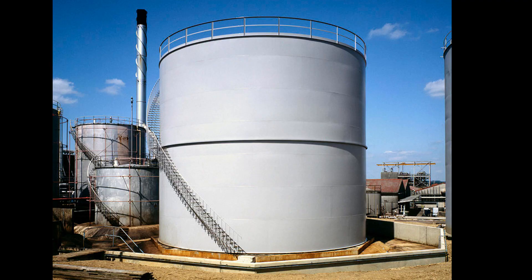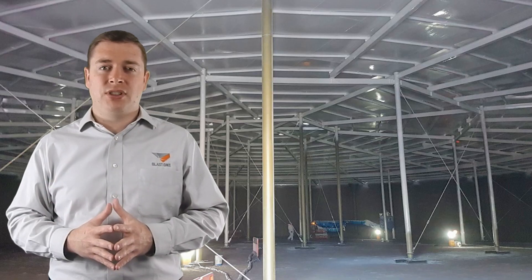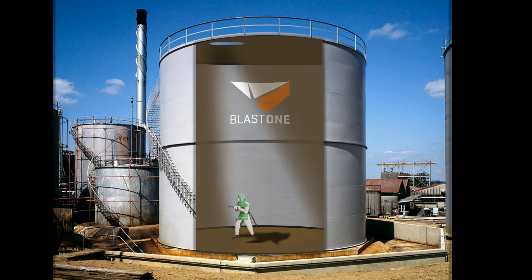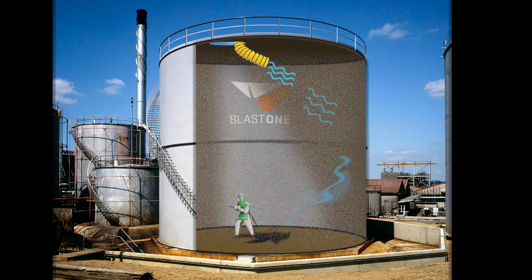Make sure the ducting is long enough to run from the manhole to the lowest possible point in the far back corner within the tank. If you're coating the tank, string a cable from the manhole to the attachment in the far back corner and clip the ducting to the cable to keep it off the floor. The most common mistake we see in the field is that ducting only extends slightly into the tank below the mouth of the manhole into the upper regions. When your ventilation method employs positive pressure — blowing air — it simply circulates the dust and vapours due to constant downward pressure, and some dust will exit but the concentration of dust will build.